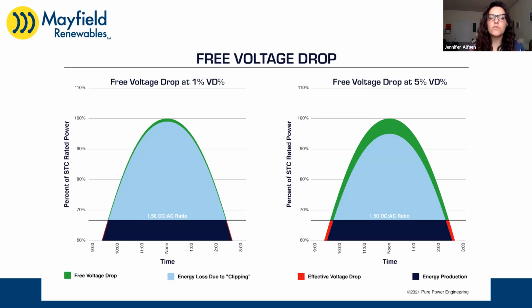So from 1500 volts to 1000 volts, how does the concept of free voltage drop change? The concept is still the same: if you're clipping at whatever voltage, if you have more power, you have that spare DC power and voltage drop. At 1000 volts you might have a little bit higher voltage drop to begin with—the lower the voltage, the higher the voltage drop. At 1500 volts, it's almost easier to maintain, so you don't have to work so hard to drop that voltage. In a way, you could say that at 1000 volts, the concept of free voltage drop is actually more so than at 1500 volts.